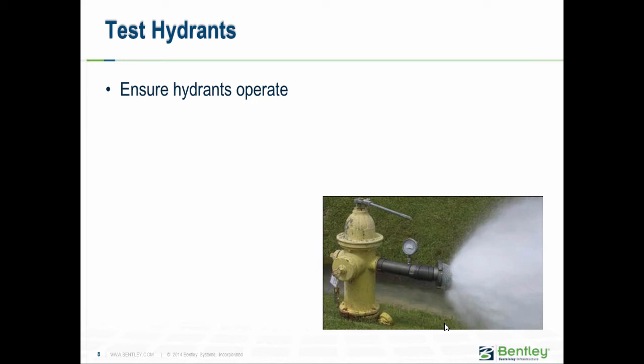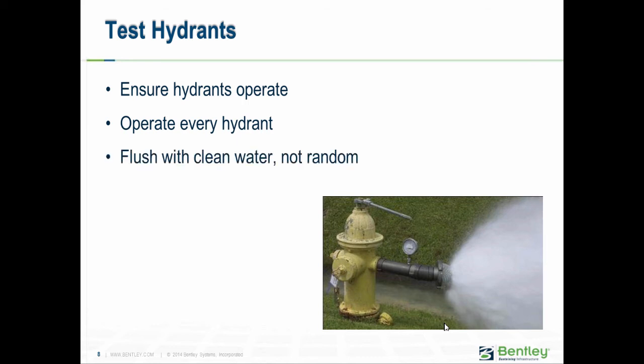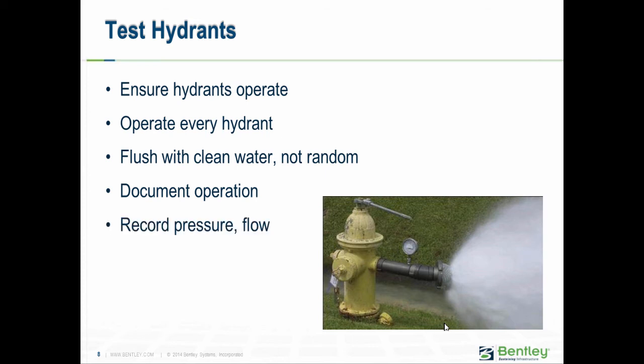Some people do flushing not primarily for water quality — that's a side benefit — but really to make sure hydrants will operate when the fire department needs them. This is a different kind of goal. You need to operate every hydrant; there are no long flushing runs. You want to flush with clean water behind you to improve water quality as a side benefit. Document operations: what's the pressure, what kind of flow can you get? With this information in an asset management system, you can look for trends — for example, if flow from a hydrant decreases suddenly, that might indicate a valve has been left closed or partly closed.